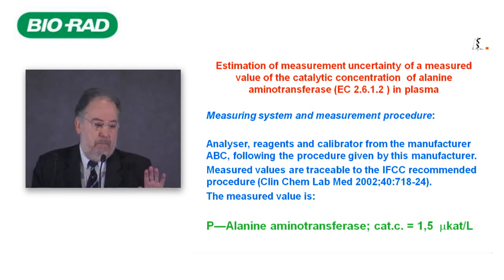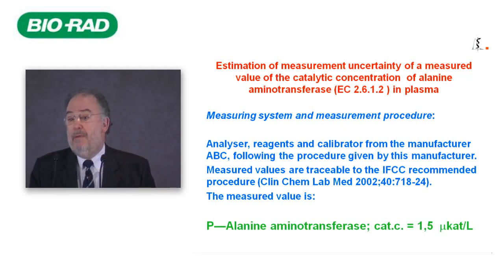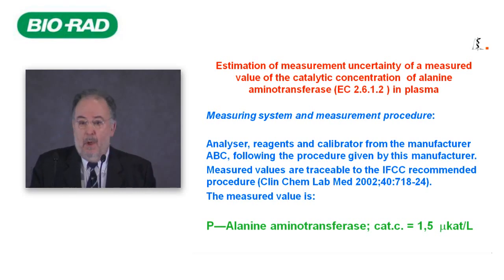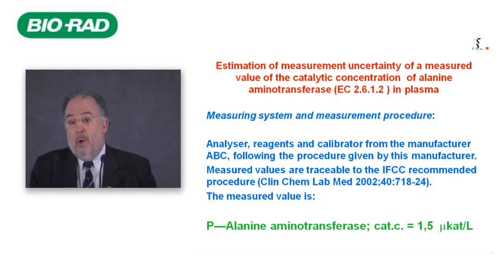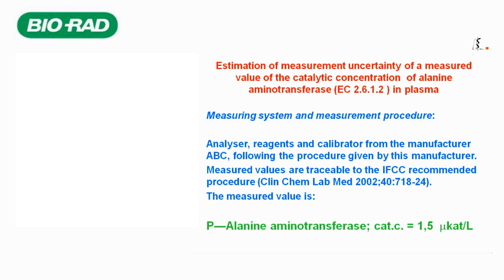I will now present a practical example of the calculation of measurement uncertainty in a clinical laboratory, using the catalytic concentration of alanine aminotransferase (ALT) in plasma. The first step is the description of the procedure or measuring system being used — for example, one analyzer following the procedure recommended by the IFCC. This gives us a measured value, which according to the VIM is not yet a measurement result.